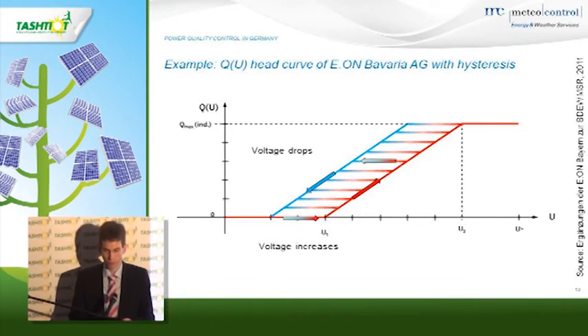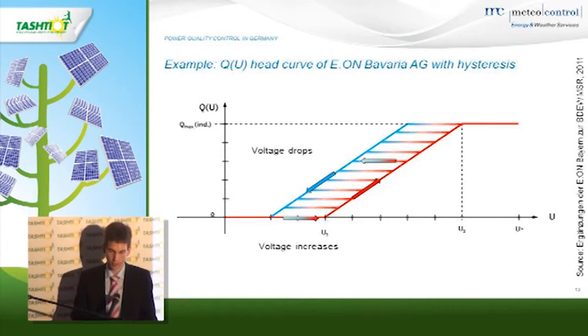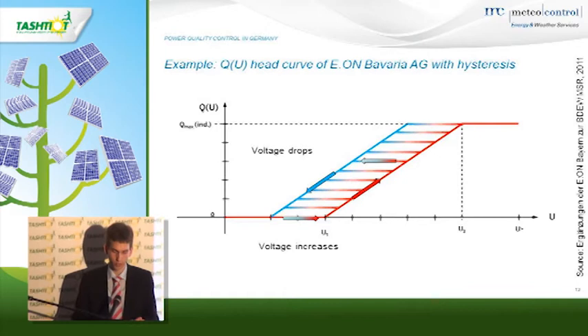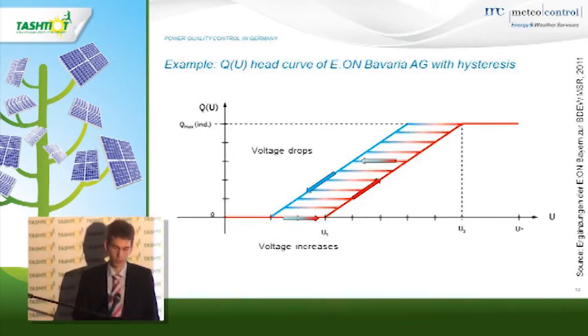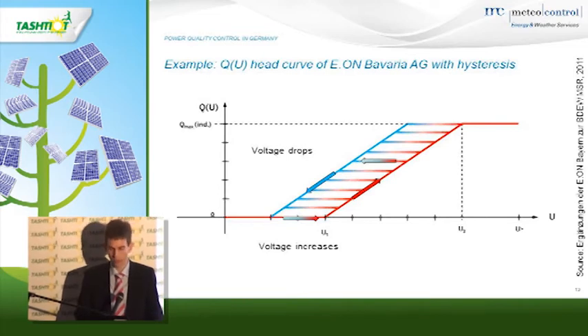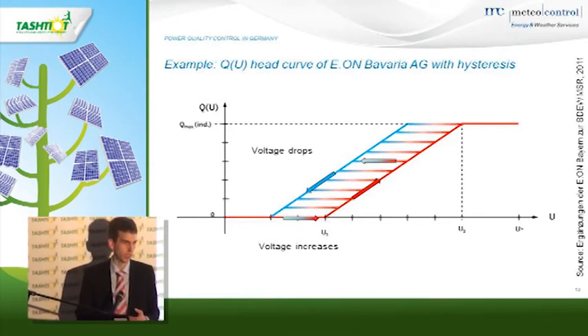And if somehow the voltage goes down again, in this specific curve we have a hysteresis, meaning if the voltage goes down, the reactive power feed-in stays constant for an amount of time, and then if it drops further, it also goes down. And the other way, if it's increasing and increasing, it goes all the way up. And somewhere the inverters are at their technical limit of supplying reactive power, and it will be limited then.